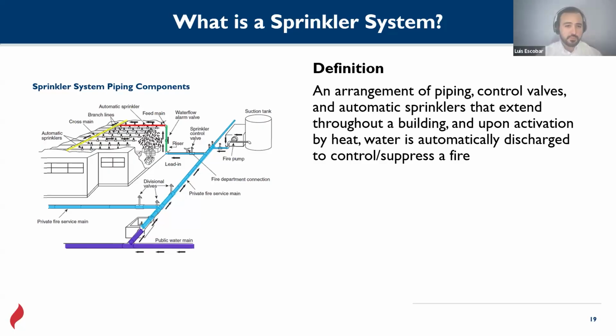Fire sprinkler systems. So what is a fire sprinkler system by itself? An arrangement of piping, control valves, and automatic sprinklers that extend throughout a building, and upon activating by heat, water is automatically discharged to control or suppress a fire. Keyword: activation by heat. We all know the activation method for fire sprinklers is obviously heat. That's why it's important to take into account temperature ratings for fire sprinklers, because if we have a manufacturing process that involves, I don't know, high release of heat, maybe a fire sprinkler can be activated by mistake.